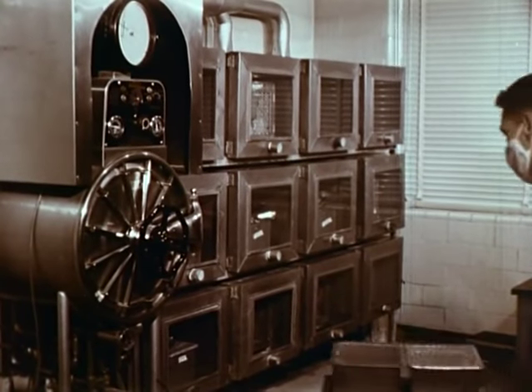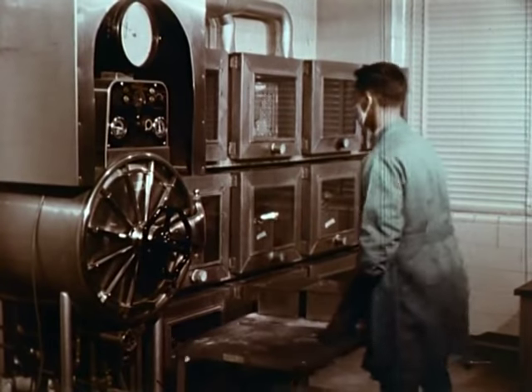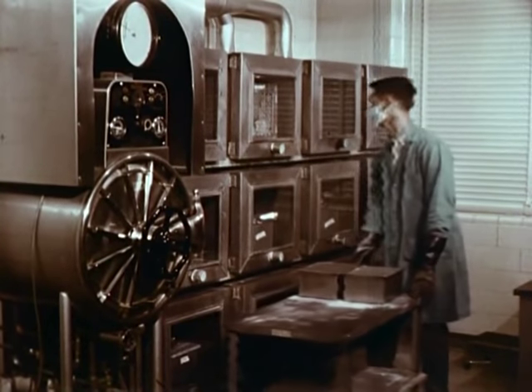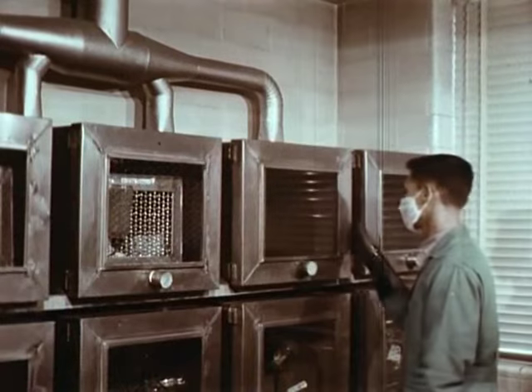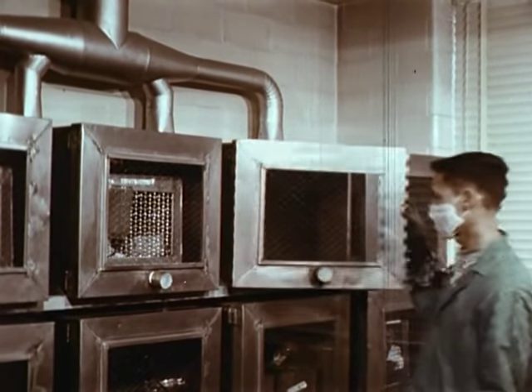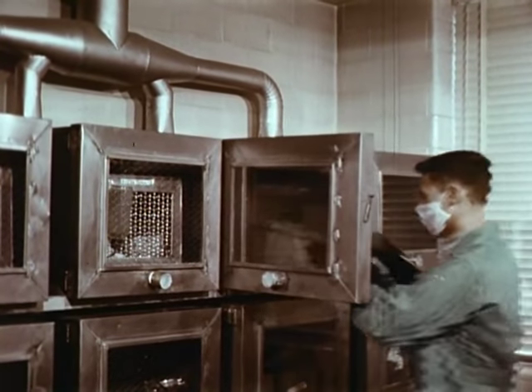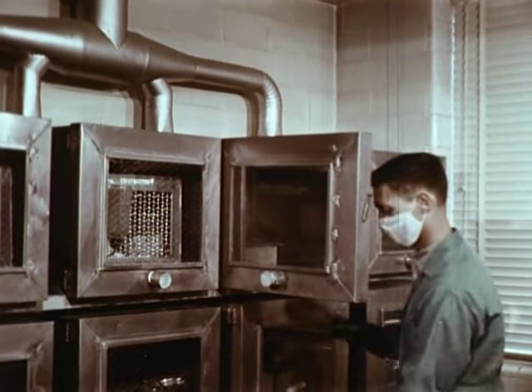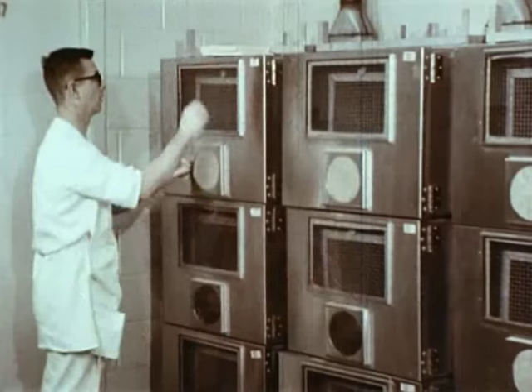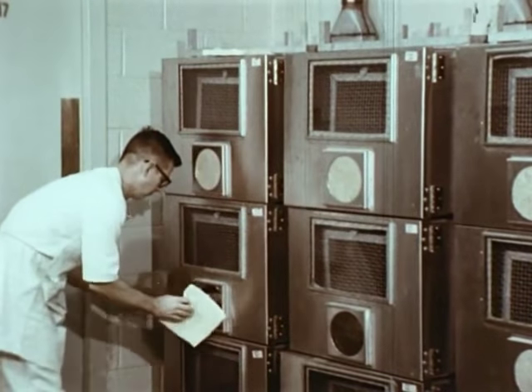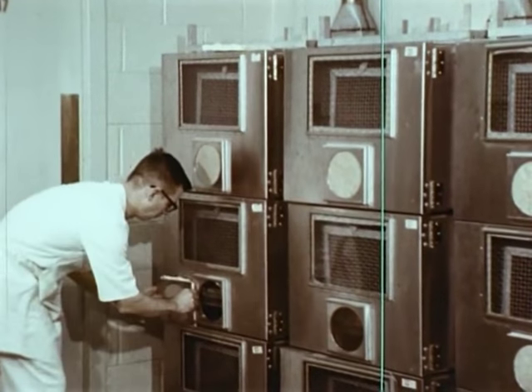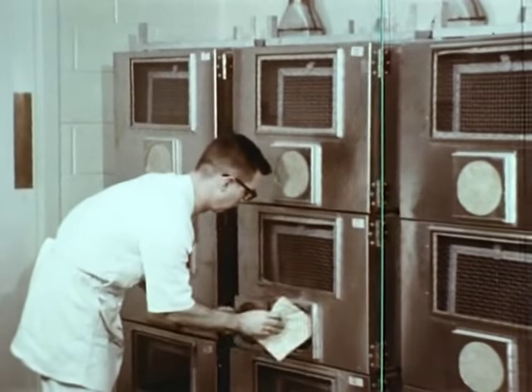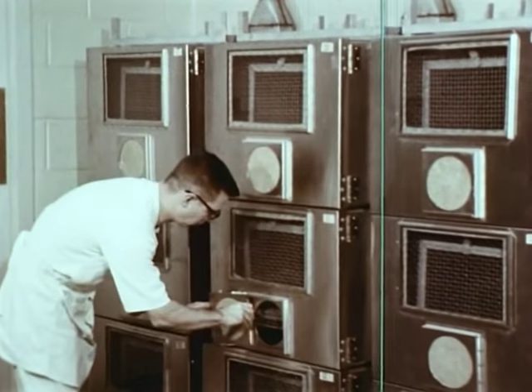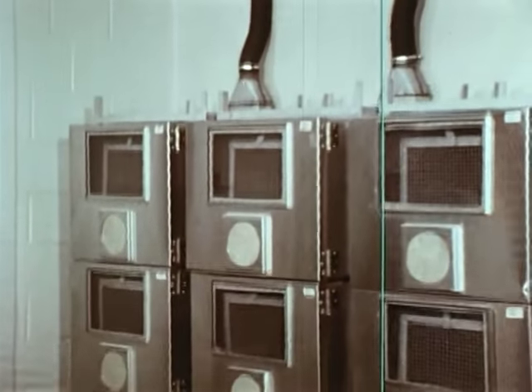Non-portable ventilated animal compartments have been found effective in some infectious disease laboratories. Each of these Horsfall units holds one or two animal cages and is equipped with a viewing window and inlet and outlet air filters. This particular version utilizes pads of spun glass for air inlet filters. The exhaust air, after filtration, goes to a common exhaust manifold. Cages of this type must be decontaminated in place.